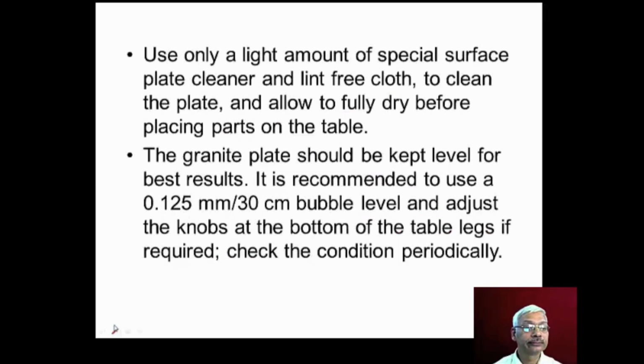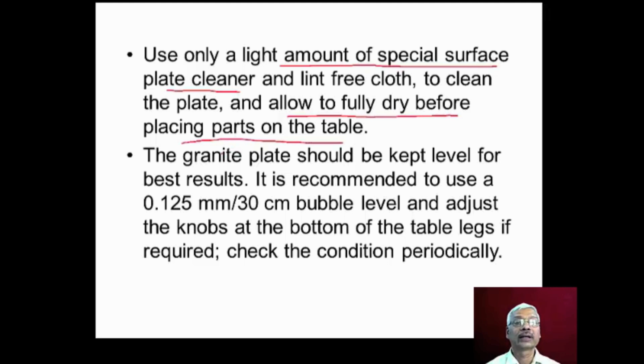We should use only a light amount of special surface plate cleaner and a lint-free cloth to clean the workpiece table surface, and we should allow it to fully dry before placing the parts on the table. The granite plate should be kept level for best results. We should use a 0.125 millimeter per 30 centimeter bubble level, and we should adjust the knobs at the bottom of the table legs. If required, we should check this condition periodically.